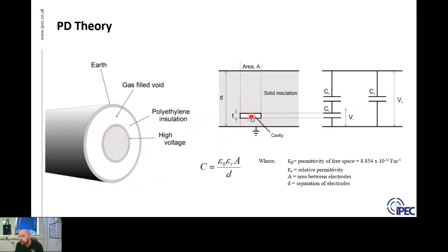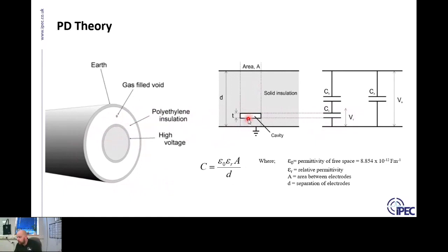As the energy in the power cycle increases, this small cavity or defect area doesn't have the ability to resist that stress, and you get a very small partial discharge occurring at this defect point. So the partial discharge is occurring at the actual cavity — not across the whole insulation — it's a very localized discharge at a localized stress point.